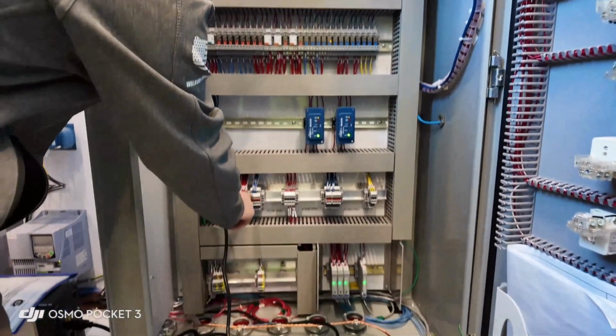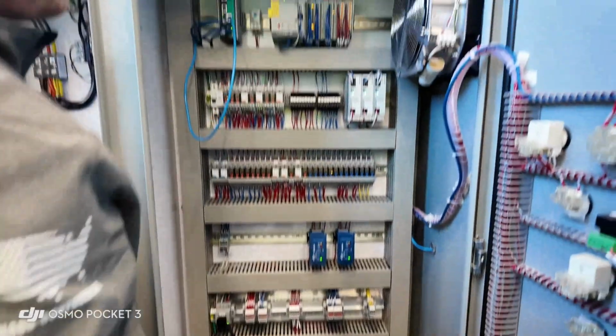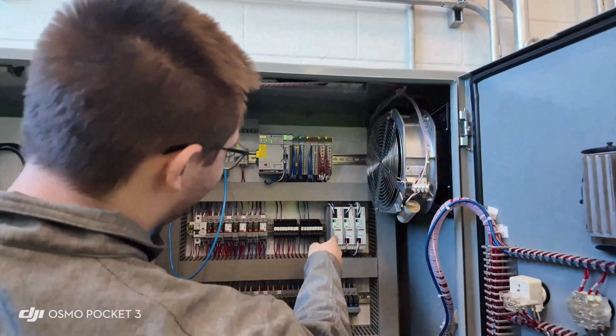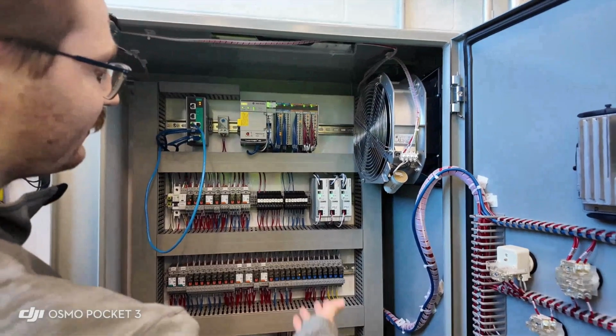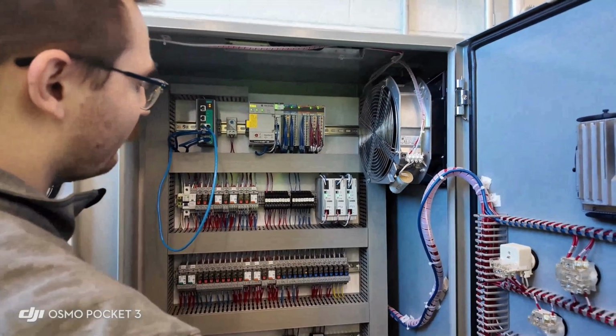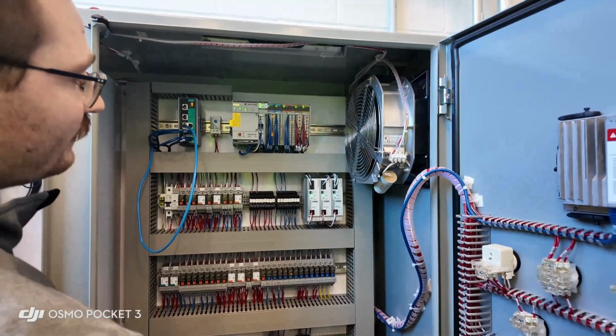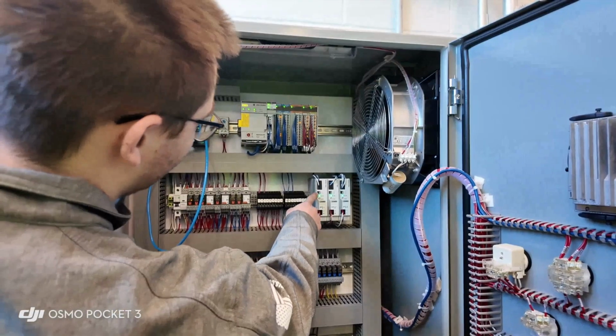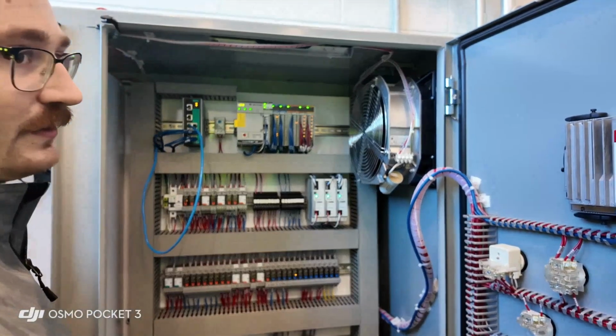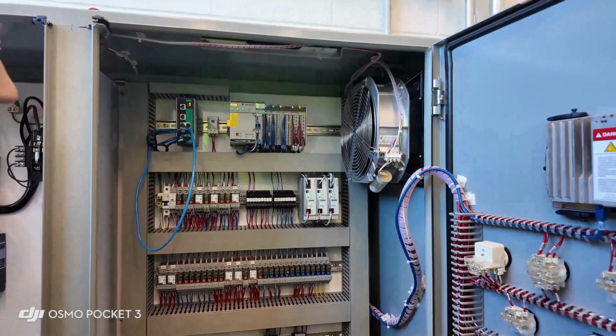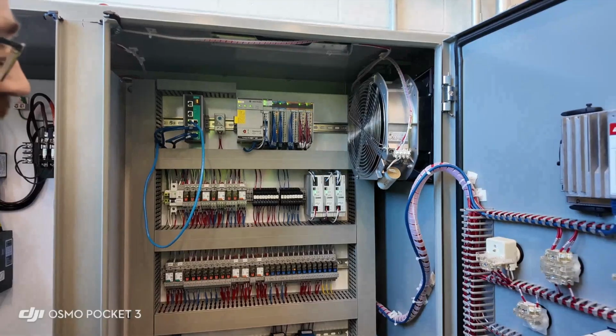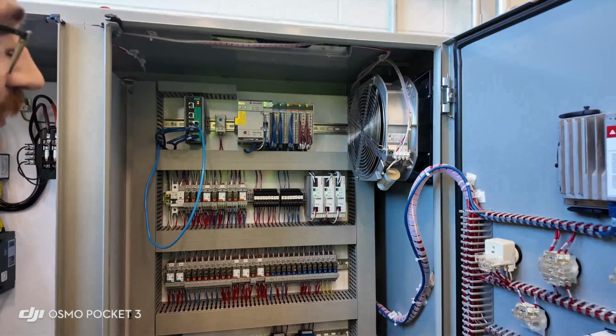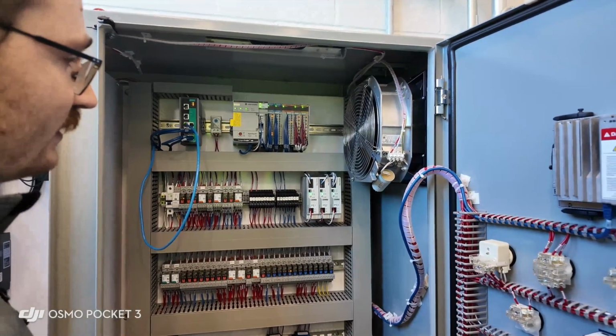This is coming off of PS power supply 2. We have 3 power supplies. These are 5 amp power supplies. You feed them with 120, they output 24 volt. In the future, if you have issues with power supplies, they actually have built-in contacts, so you can monitor if one of the power supplies goes bad. It'll use the contact, and it could be used to display any issues out to something like SCADA.